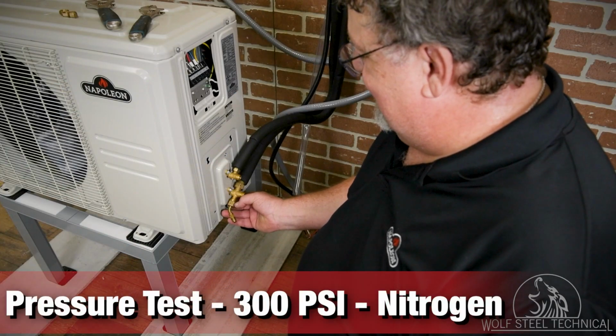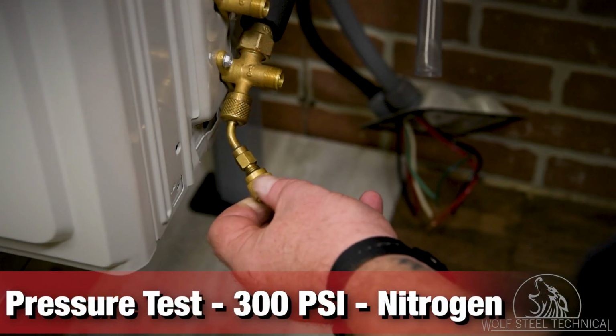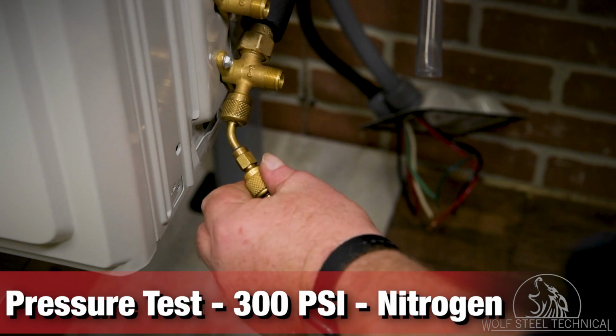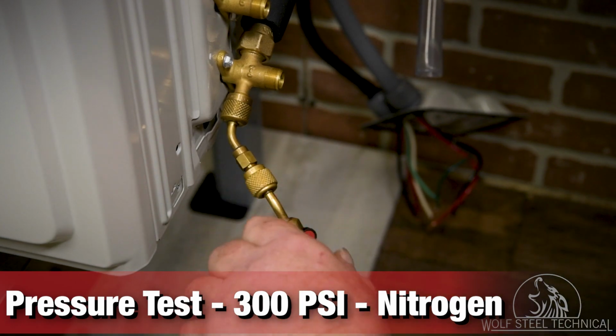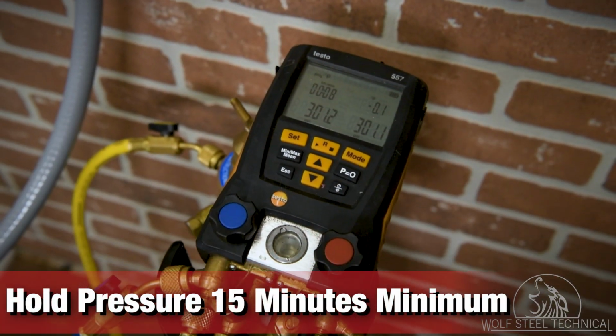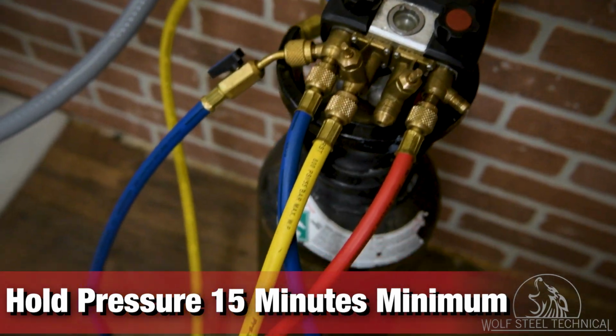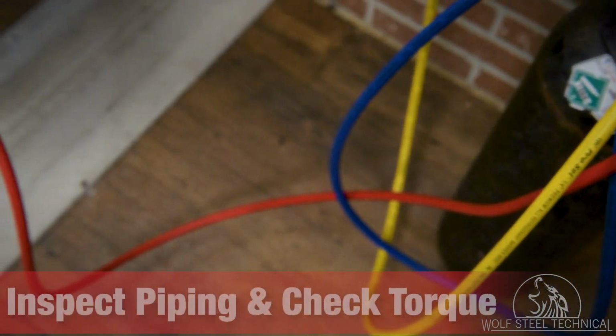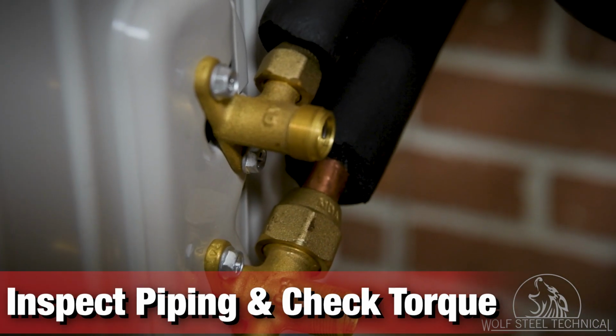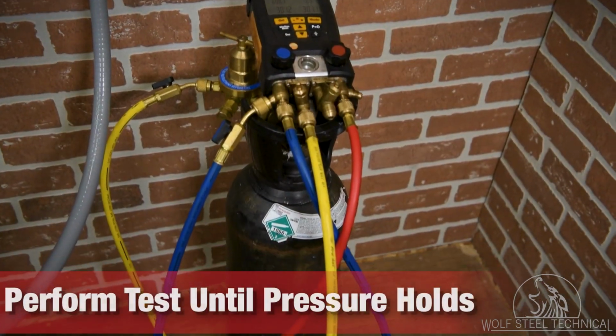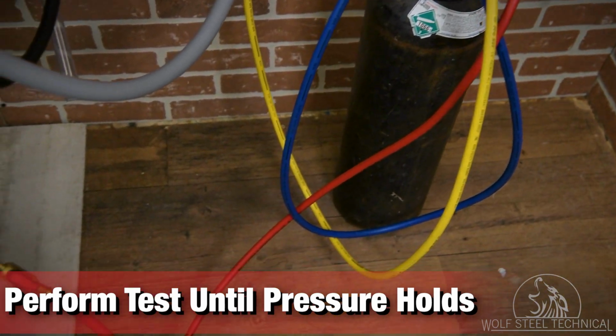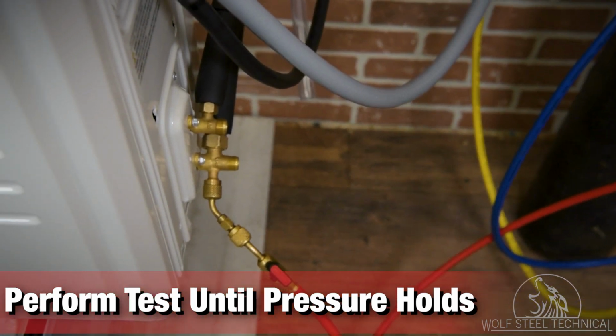Next, perform a pressure test on the system by charging it with 300 psi of nitrogen. Allow the nitrogen to sit in the system at 300 psi for a minimum of 15 minutes and monitor the pressure for any drops, indicating a leak. If a pressure drop is observed, inspect the piping and check the torque specs at each connection to correct the issue. Once corrected, perform the pressure test again until pressure holds for 15 minutes or more.